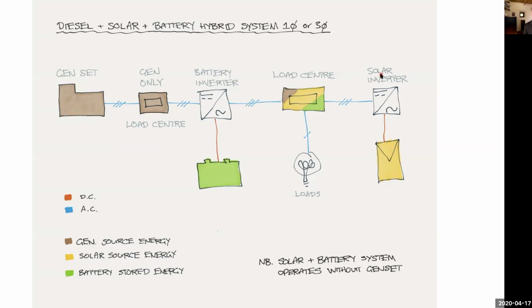So over here, the solar inverter. The solar inverter can output AC power, and I've drawn this as three-phase, but it could be single-phase, it doesn't really matter. That power will first supply the loads. Surplus power will flow in the reverse direction into the load side of this battery inverter. Now, not all inverters can accept power on their load output. So don't assume this is the case.